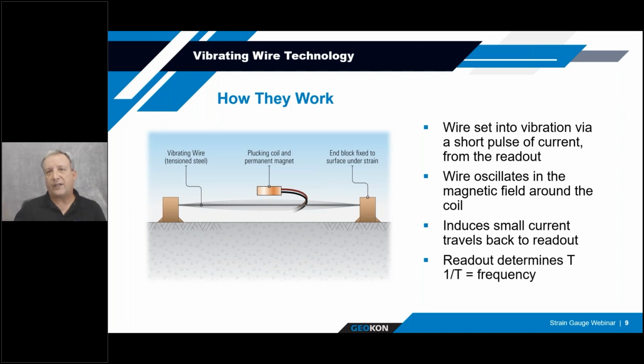So with a guitar string, and I'm not a musician, if you tighten or loosen that guitar string, you're going to get a different sound and a different frequency. Similar to that, with the vibrating wire, if those ends move in or move out, when that wire vibrates, you're getting a different frequency from it. So the idea is that we've got a plucking coil and a pickup coil that's centered on that wire. And once that coil is energized to pluck that wire, the pickup coil receives the vibration and the frequency and transmits that up through the signal cable to a readout or data logger. And that way you can determine from the calibrated values the change in position of that element. That's the basic rundown of it.